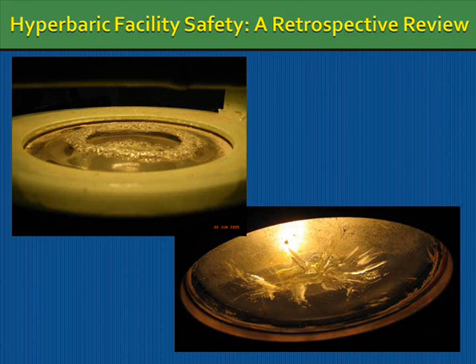Two very scary pictures, and they don't really present very well here, but those are windows of chambers. Okay, you can say to me, you clearly see the visual damage and you can be convinced that obviously these are not safe to be used. But let me tell you right now that both of these chambers, and there's a date stamp over there on this one, this is from fairly recently, but that was 2004. And both of these chambers are still running with those windows as they are at the moment. Clearly, the windows are in distress. Clearly, there's an accident waiting to happen. But sometimes the people just don't actually take on the responsibility of understanding what they're dealing with. If you can imagine, even at a very low pressure, what the impact will be if one of these windows has to rupture.